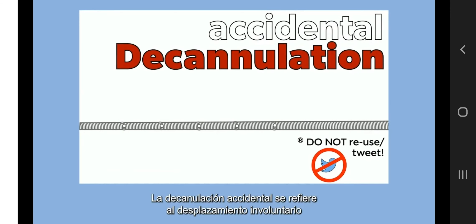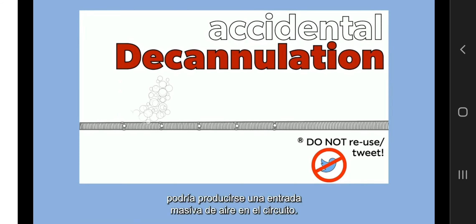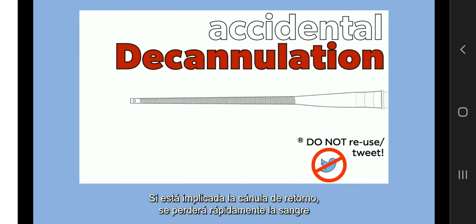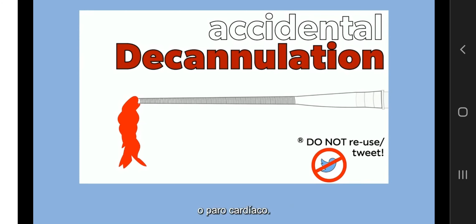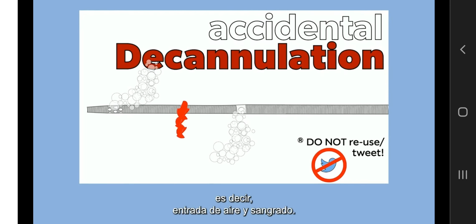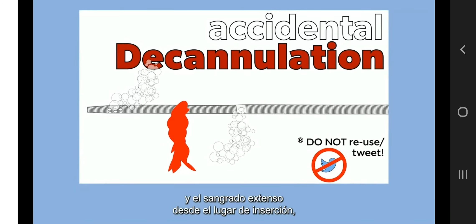Accidental decannulation refers to the unintentional displacement of the cannula during an ECMO run. If the drainage cannula is involved, this could induce massive air entrance within the circuit. If the return cannula is involved, blood will be rapidly lost, leading to exsanguination with risk of hemorrhagic shock or cardiac arrest. With bicaval dual-lumen catheter displacement, it is easier to have the first scenario due to exposure of proximal drainage baskets, but both situations may coexist, so air entrance and bleeding. Moreover, with any catheter, inadvertent decannulation results in sudden discontinuation of extracorporeal support and extensive bleeding from the insertion site. This risk is increased with an arterial return cannula.